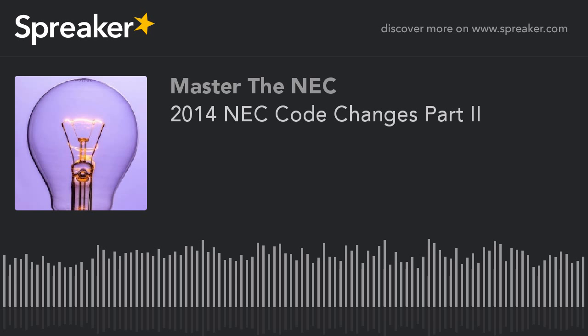Because if you know you're going to have an EV circuit in there, then you've got to meet 210.17. So this is like, well, we're going to cover the people that don't know that. And that's why we're going to have a separate receptacle for each space, and why the receptacles can only supply outlets in the garage. You get where I'm going with that? So now they feel like by doing this, it also allows you to potentially plug in one of those class 1 type EVs in there and not have an issue. Because you don't know what people are going to buy. Heck, I could go out and buy an EV vehicle right now since my truck's all dented up.